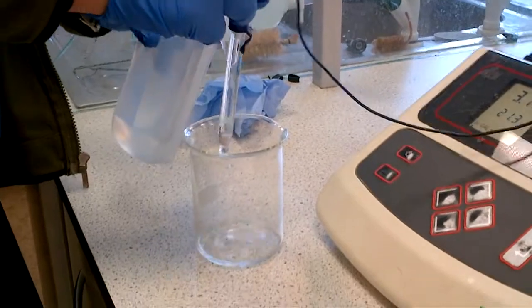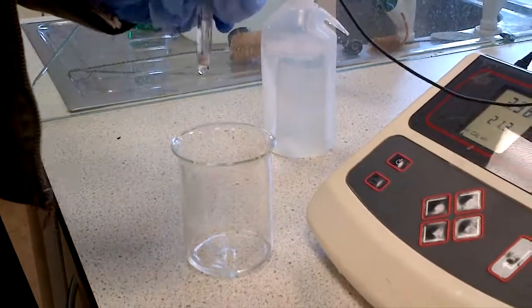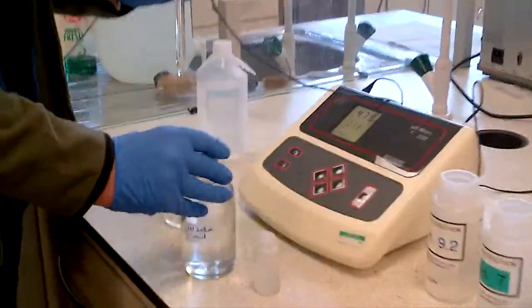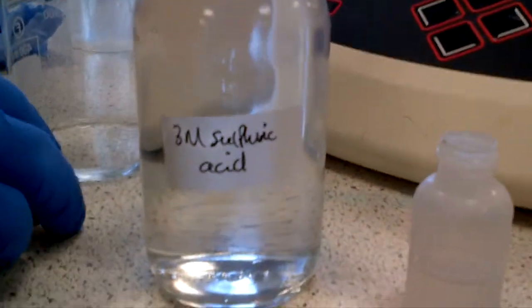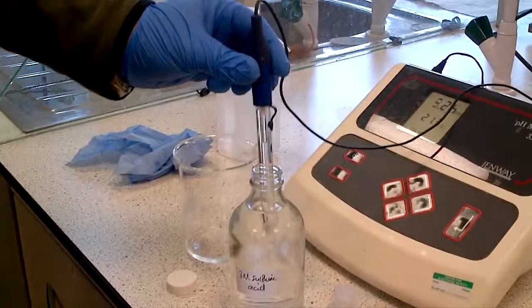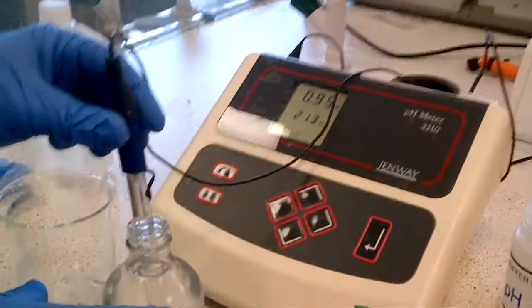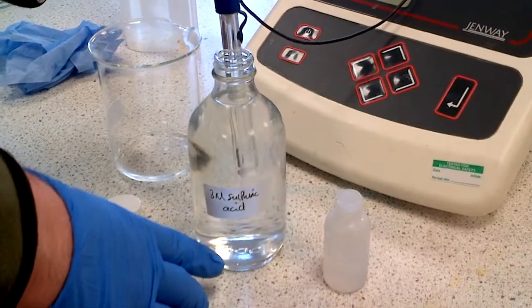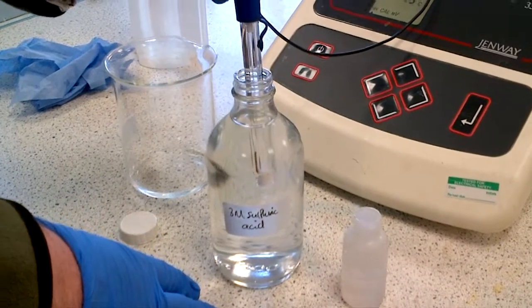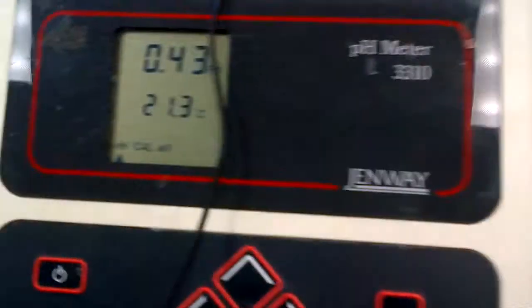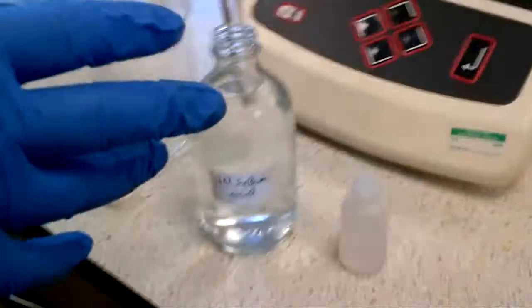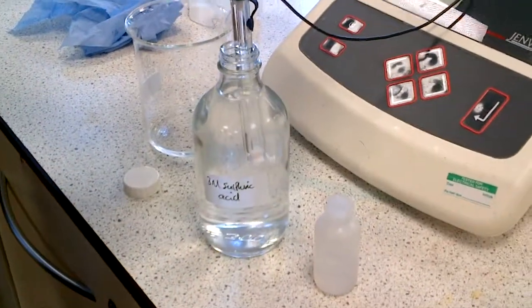We're going to show again how you would measure the pH of a solution after calibration. Again, wash with water, dry with tissue paper, and we're going to measure the pH of this general lab stock 3 molar H2SO4. We'll shake off any water, we've dried it with tissue paper, and we'll place it in there. Again, we're not being too rough with the electrode, dropping it down to the bottom of the bottle and shattering the electrode. We place it inside and we see we're reading about 0.46, 0.4 pH. Let it get down to a common value.